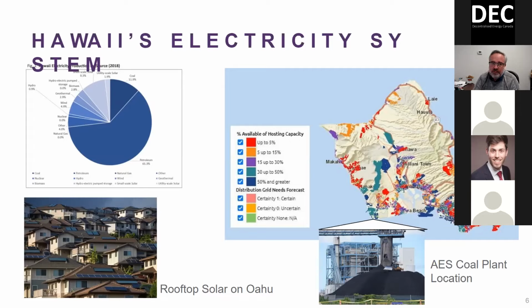So if you want to put solar on your house in those areas, which is most of where everybody lives now, you need to put a battery on the system and install a zero export controller, so that any excess solar during the day is put into your battery. If your battery is full, the solar gets shut down and does not export onto the grid. That's spreading across the island, which is why they put these programs in place, trying to get more individual batteries alongside solar. Effectively today, that's the only way to install solar—with a battery alongside it to control its output onto the grid.